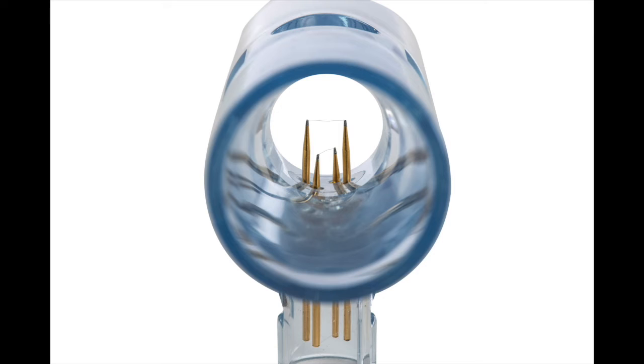Sometimes end users or whoever's cleaning the flow sensors want to stick Q-tips through to clean it, and it'll break off these wires. Sometimes they can get caked off with a lot of medication. So this is maybe my main issue here. However, if I pop in a new flow sensor and it's not working, it might be my flow sensor cable, which I'll go over.